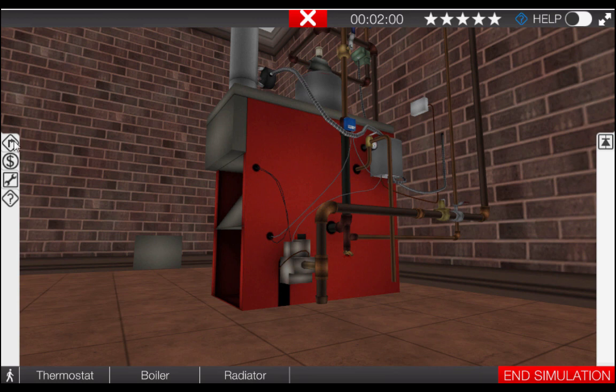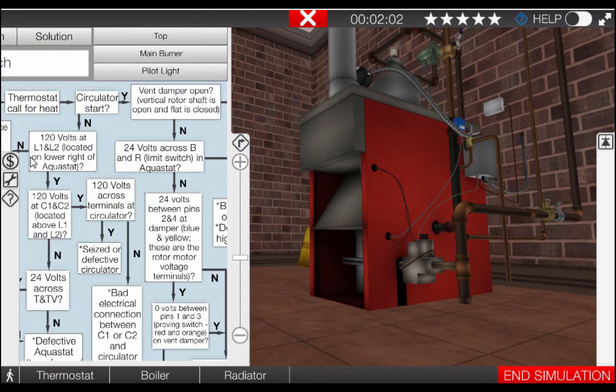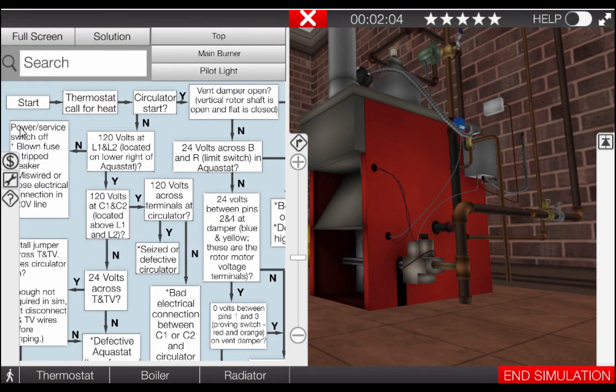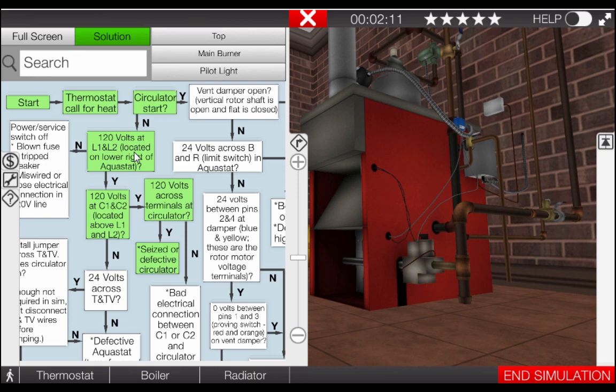Let's take a look at the troubleshooting flowchart to review the steps covered so far. Click on the top tab on the left of the page to open it. Following the flowchart, we can see that the burners have ignited yet the circulator does not operate. Our next step is to measure for 120 volts at the L1 and L2 locations on the lower right of the combination aquastat.